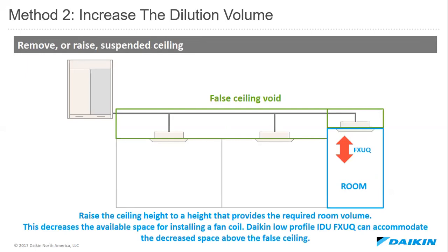Another thing we could do is lay out the rooms differently. Let's assume our smallest room was too small. We could raise the ceiling height to provide the required room volume. This would decrease the available space for installing a fan coil, so we would go to a model indoor unit that would accommodate the decreased space of the false ceiling void. In this way, we've also, once again, used method 2 of increasing the dilution volume by raising the ceiling in the smallest space.